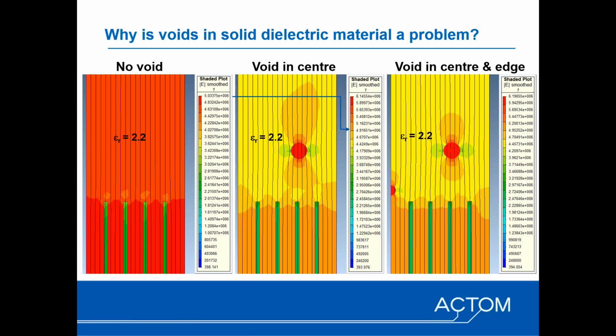One effect of the partial discharge is that you also get material erosion, and then over time the material will degrade, and you will eventually get a flashover between the 2 electrodes. This is even true for a void that is trapped on the surface of the electrode.